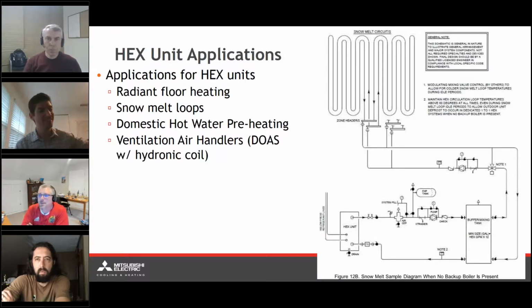Exactly. Yeah. Does the volume of the water in that loop make any difference to whether you need a buffer tank or not? Like if you have a big loop going out to the building. So I'm going purely off of the application note and the design criteria, and that's just one of the components that is required in the system. So I can't really say one way or another whether the volume of the water is going to diminish the necessity. But just thinking out loud, I think that may play a factor. And I think as a result, the buffer tank was just made a flat requirement across all different system sizes.